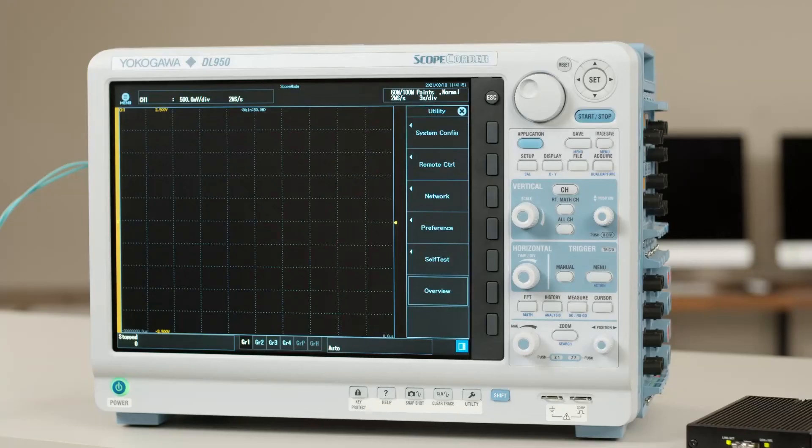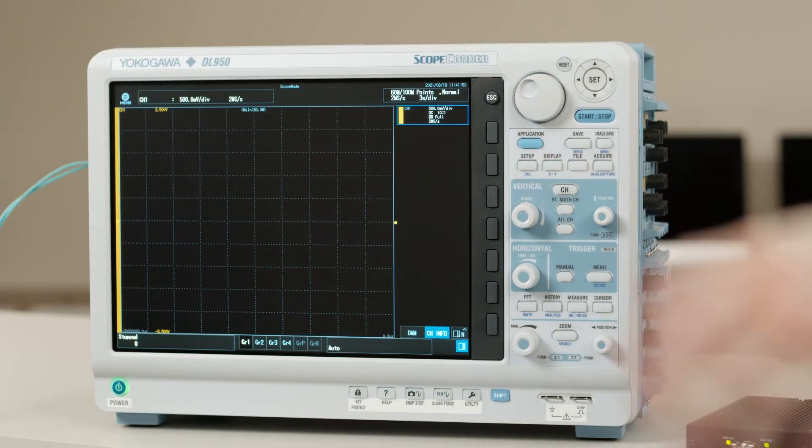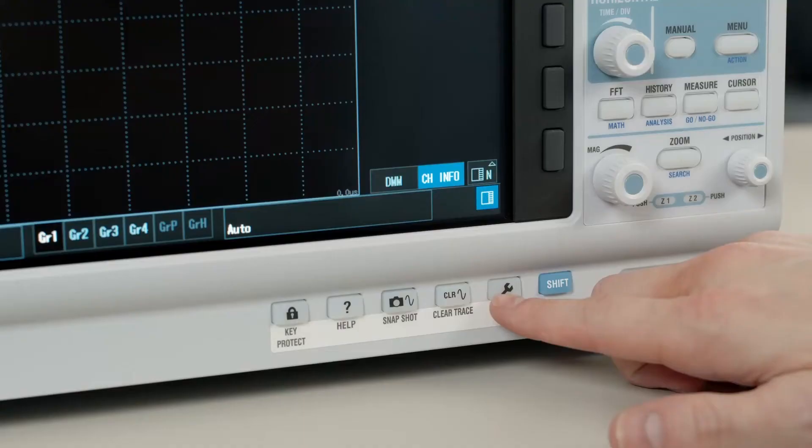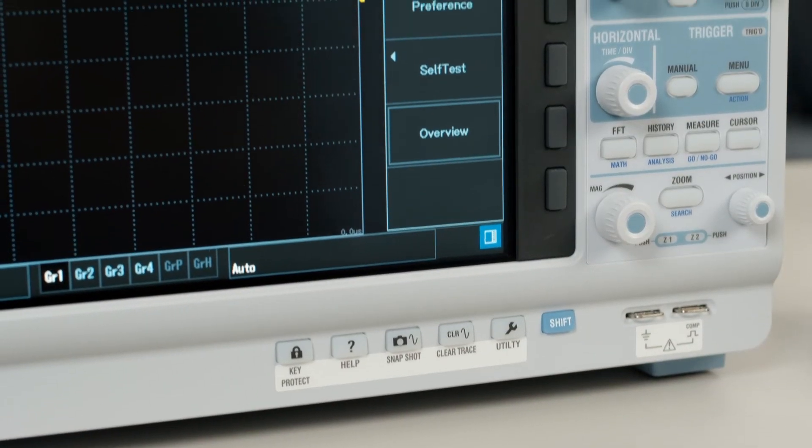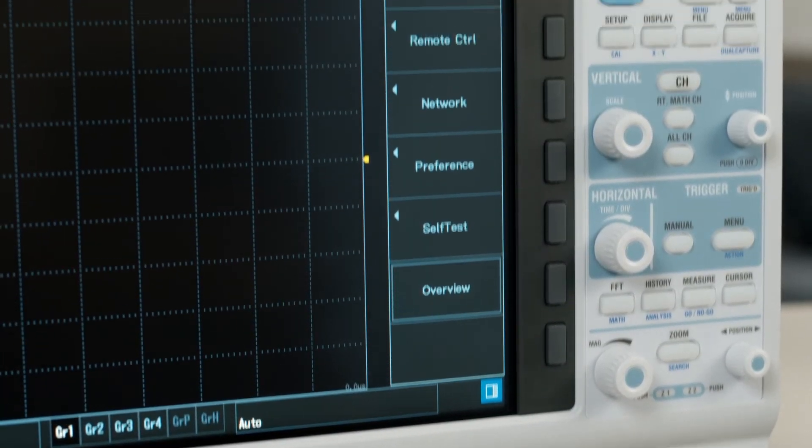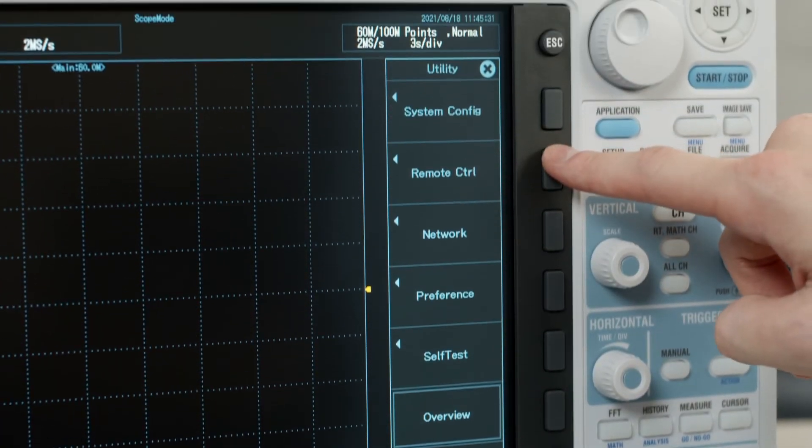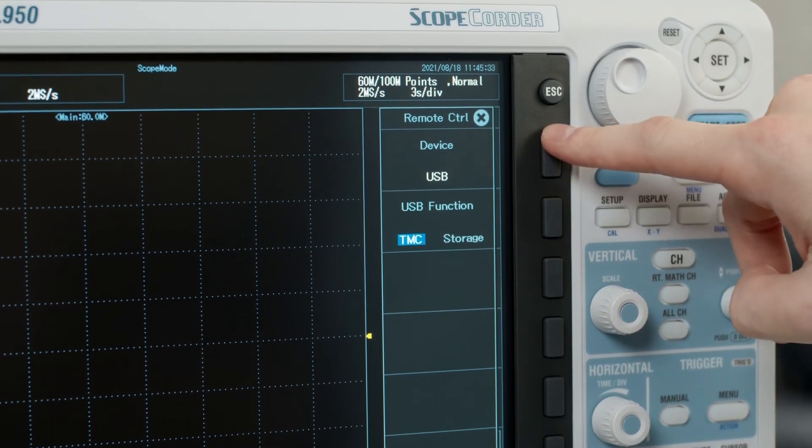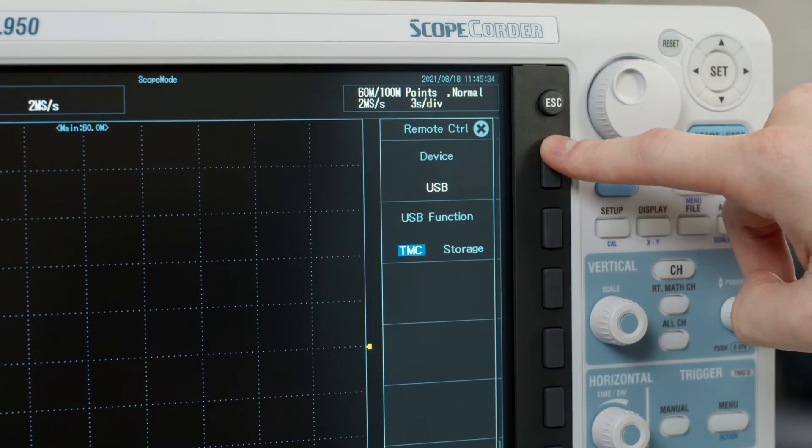Now that we've got the hardware set up, we'll adjust the network settings on the DL950. First, press utility, then press the remote control soft key. Then select device and press network.